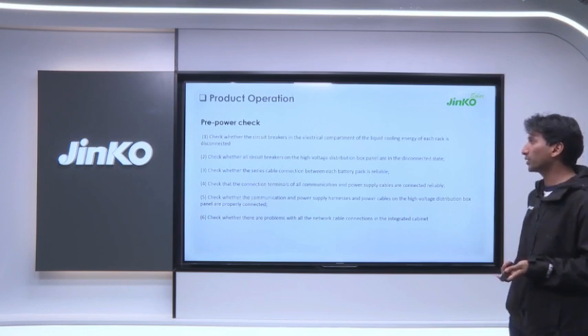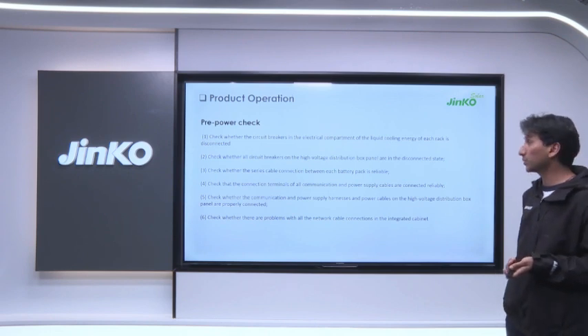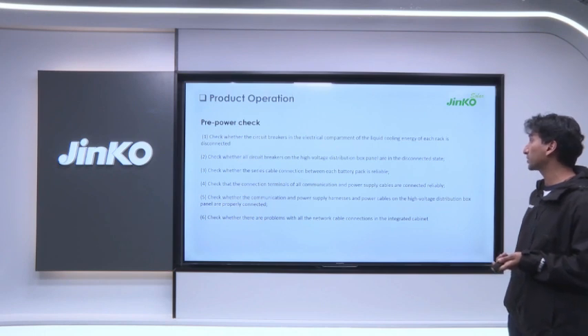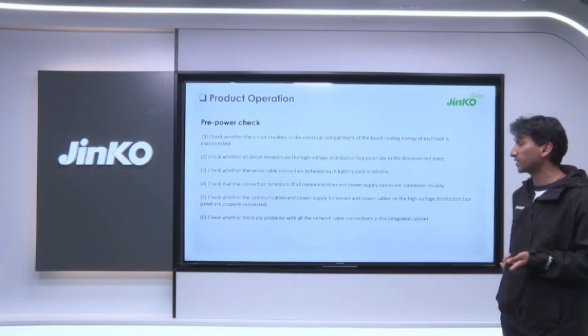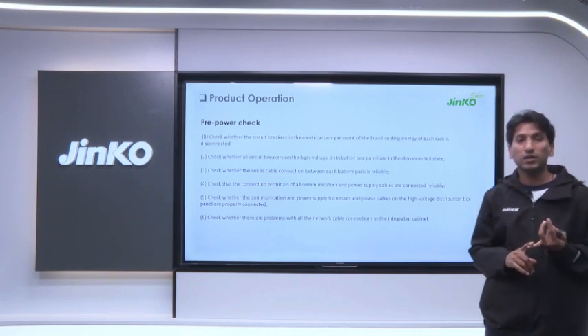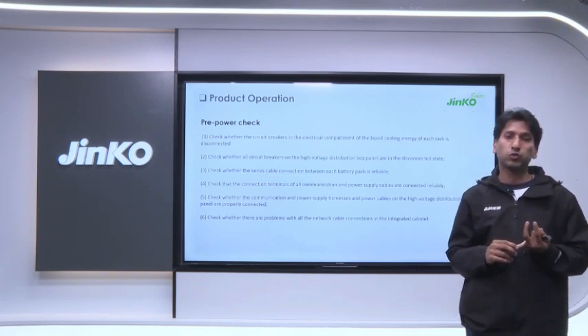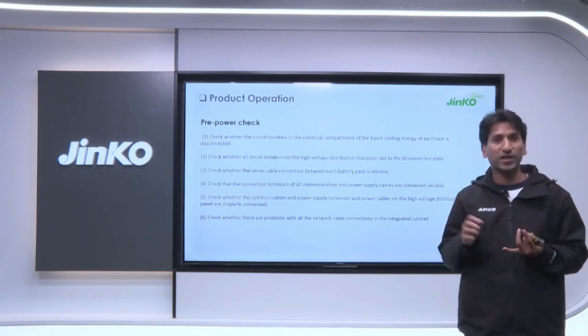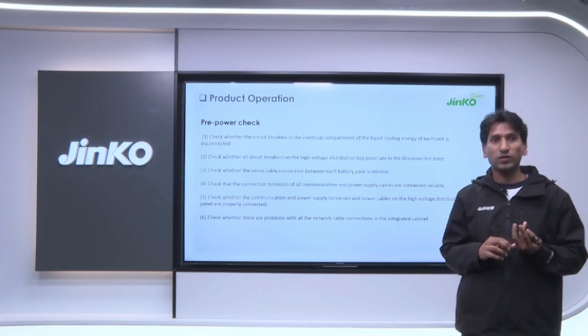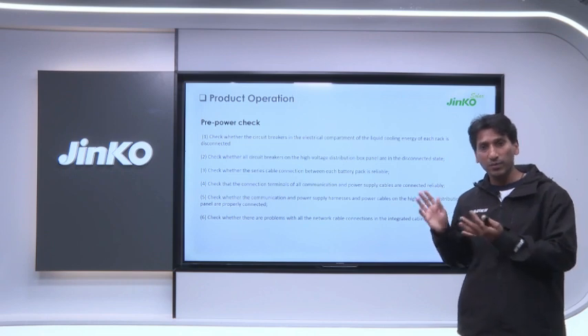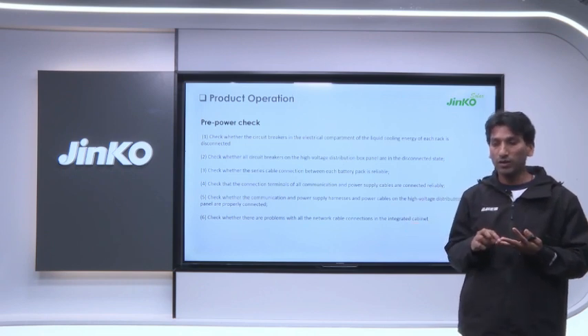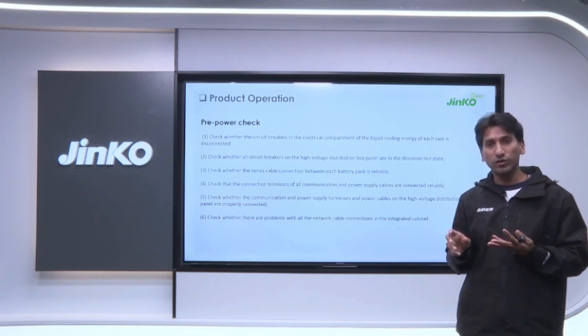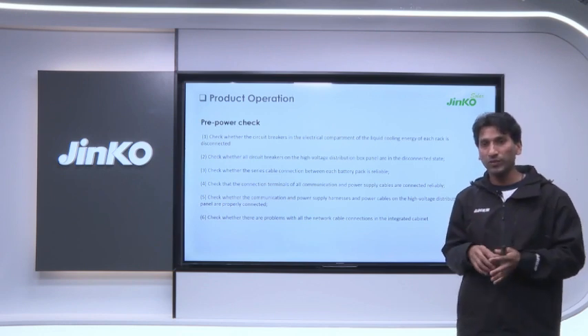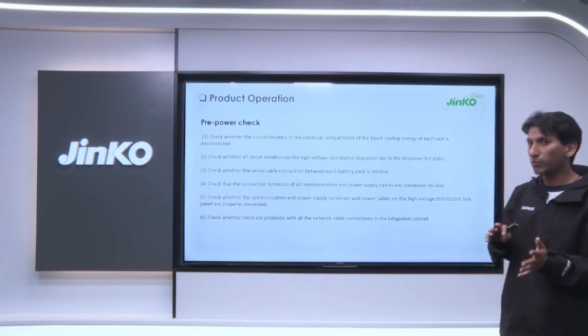Pre-power checkup. Now we are all ready to power up the system. Before we power up the system, we have to check whether all circuit breakers in the electrical compartments and the liquid cooling energy of each rack are disconnected. We have to make sure that the switches in each of the racks are disconnected before we power up. And all the circuit breakers, all the switches inside the integrated cabinet, are all switched off. All the switches for the liquid cooling system and for the fire extinguisher system are all closed. Everything is closed before we power up the system.